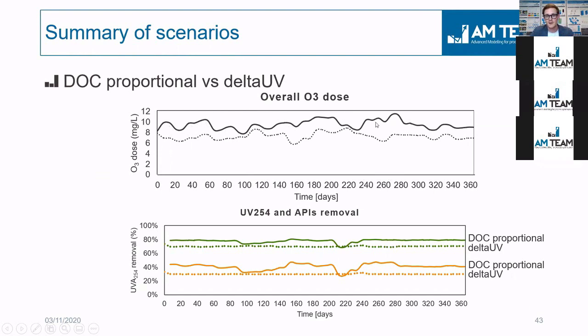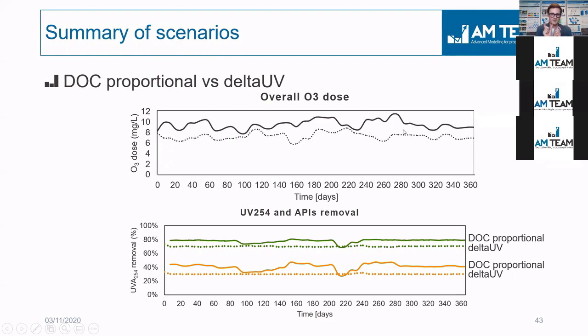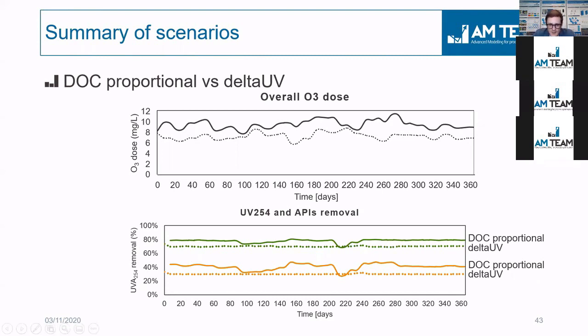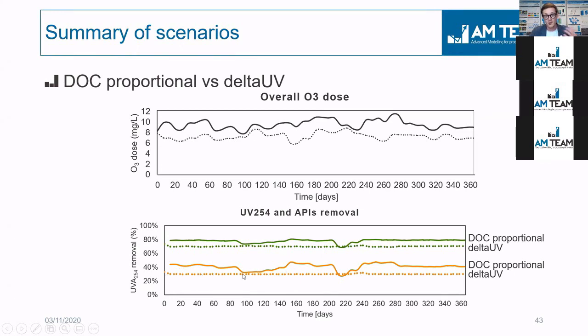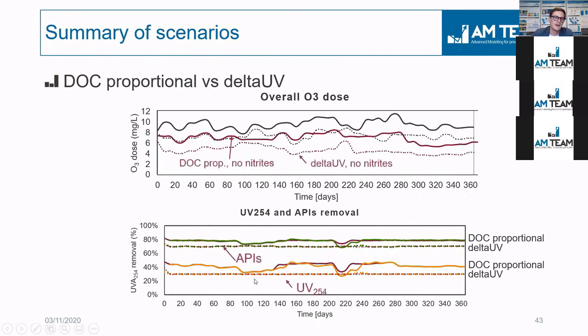And the required ozone as function of time, and also as function of control strategy. For example, the solid curve here is the DOC proportional, while the dotted line represents the UV, the delta UV control. Let's control at the 30% removal of UV before and after, with two sensors or one sensor. And then you can see the corresponding API removal, the green line, and the corresponding UV removal. And in the controlled scenario, of course, you are just very stable at 30%, because you are controlling your plants at this.